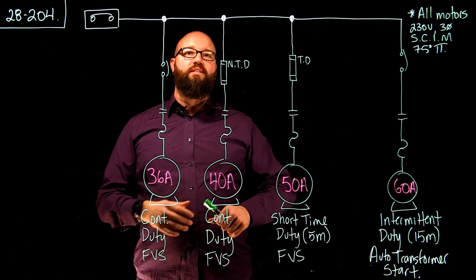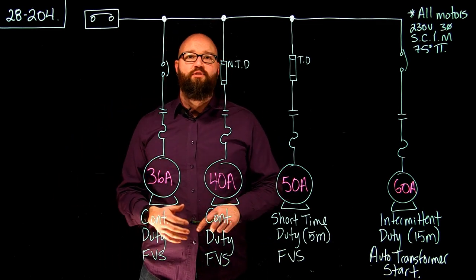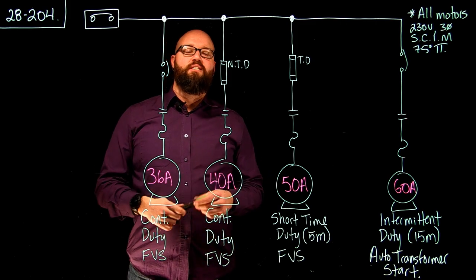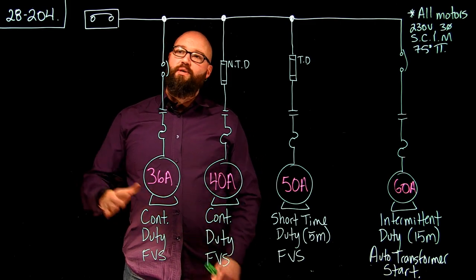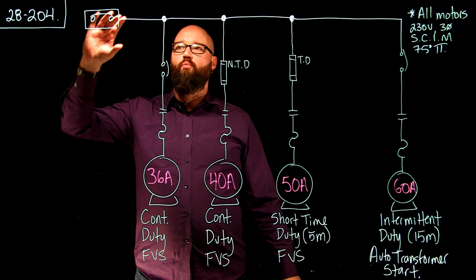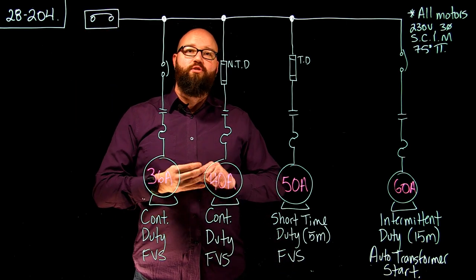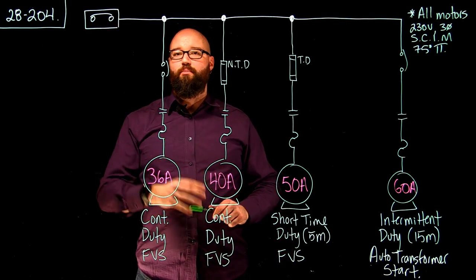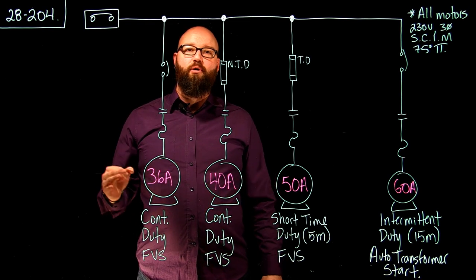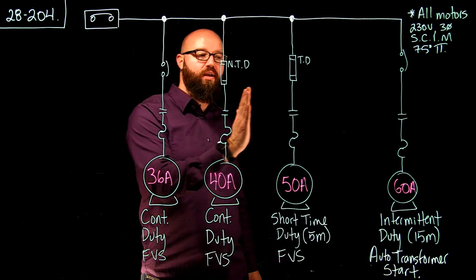Rule 28204 is a little bit difficult to interpret, so I'm going to break it down into an easy interpretation. What it effectively says is: when we protect all of our individual motor branch circuits with one main overcurrent device, we are going to go to Table 29, and we are going to apply the multiplying factor from Table 29 to each one of these motors.